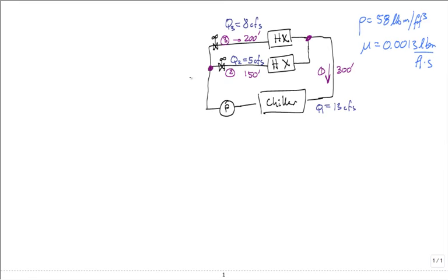Our goal is to have velocity always less than a maximum of 10 feet per second — that's often a good design criterion. Water moving through a system very fast makes noise. In a building where people are taking tests or working in office space, you don't want to hear fluid rushing through the duct or pipe system. High speeds also cause pipe erosion, so low velocity is a design criterion.